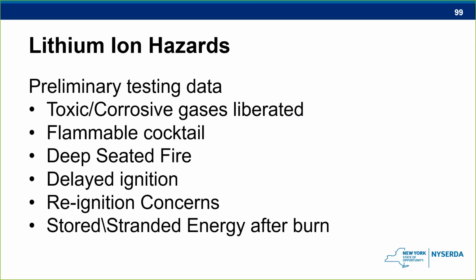So there was some preliminary testing data that was done by NYSERDA. They joined up with Con Edison, which is the local utility company that supplies electricity to most of New York City. And during this testing, they took a battery and they abused it. They abused it by heating it up, and as a result of all of that, they started to realize that there was some off-gassing taking place that was toxic and corrosive, and those gases were being measured. But in every fire that we go to, we usually deal with toxic and corrosive gases, and any firefighters that are on here know exactly what I'm talking about.